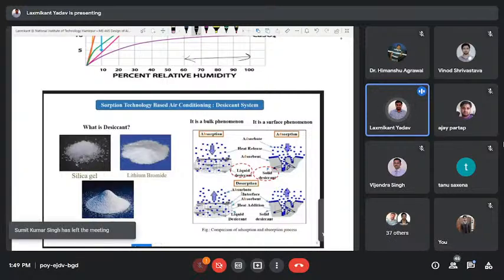This is the liquid solution, either a lithium chloride water solution or a lithium bromide water solution, and these blue ones are the moisture or vapor particles that will be absorbed by the liquid desiccant. The right side is the desiccant like a silica gel particle. It is porous, so there will be a diffusion of moisture on the surface, and a single layer or multi-layer formation of moisture molecules on the surface of this silica gel particle or any desiccant material particle. During absorption and adsorption, heat is released, and that heat is called the heat of absorption or heat of adsorption. During absorption or adsorption, heat is released in the solution and similarly on the surface, so that heat raises the temperature of the air as well as the desiccant surface.